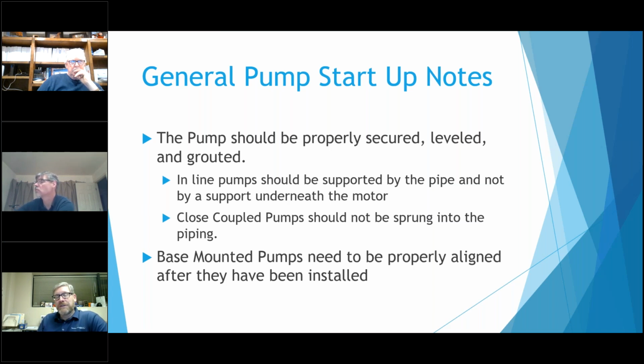I think I've seen it done. It seems to make it a lot easier because it tells exactly where to hit it and where it needs to be moved around. But it's not exactly required for most of the couplers, except for the hydro coupler. That's that orange one. The minimum that you can do with that is to dial indicate it. You do it because the tolerances on those are so tight and so small that any little misalignment can just chew up that coupler.